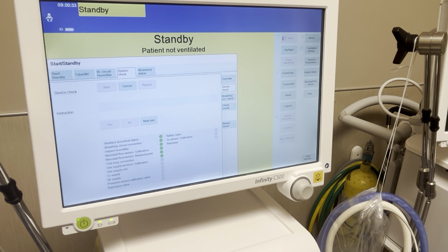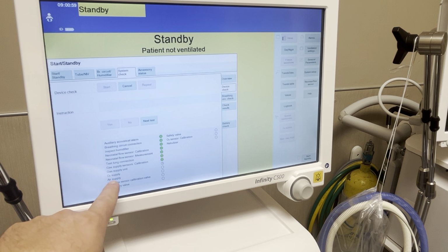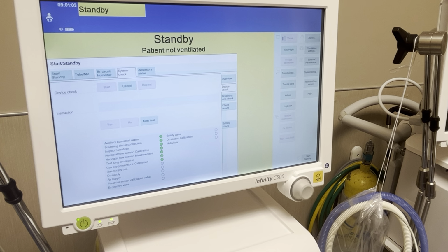While we're waiting, I guess we can talk about these green dots. If any of your tests don't pass, those dots will turn red instead of green. And when you run it the second time, it'll just run the tests that didn't pass, which is nice. So if you forgot to plug it into air and oxygen, it would skip O2 supply and air supply and call them red. So on your next run through, if you plug them in, it'll just go to those two and run those quick tests, so you don't have to run the whole thing. That's kind of a nice thing, especially if you have a flow sensor that doesn't work, or anything that fails at this point, I'd be annoyed if I'd have to start over.